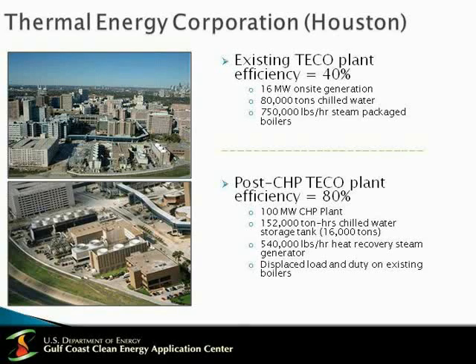Now, with the installation of the new CHP plant, the efficiency shot up to 80%. Here are some details of the plant. It is a 100 megawatt CHP plant. You have a 152,000 ton hours capable chill water storage tank. You have 540,000 pounds per hour of steam being recovered with the use of the heat recovery steam generator. And as a result of all this, you displaced the load and the duty on existing boilers, and thereby reduced emissions levels as well.